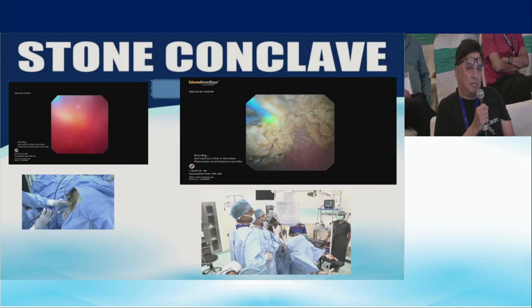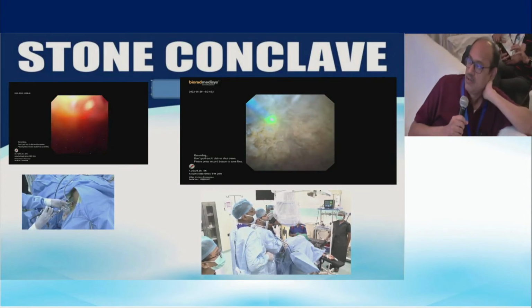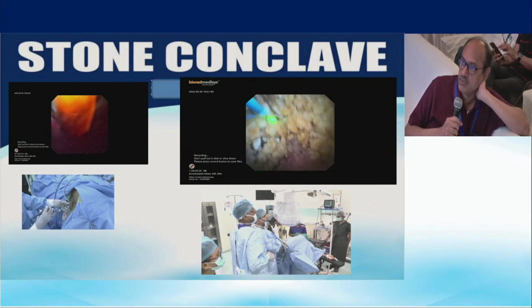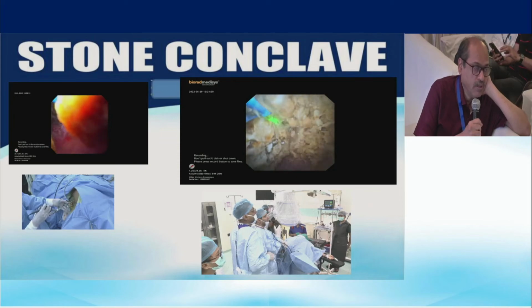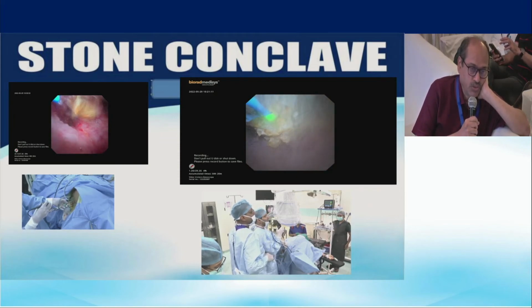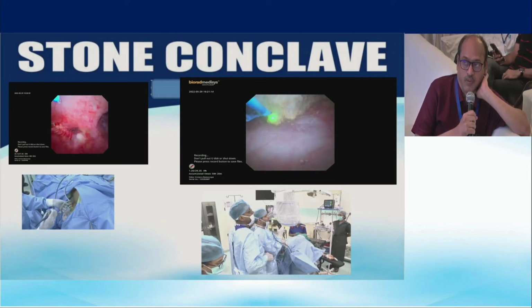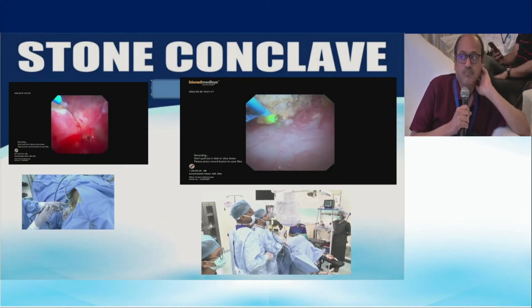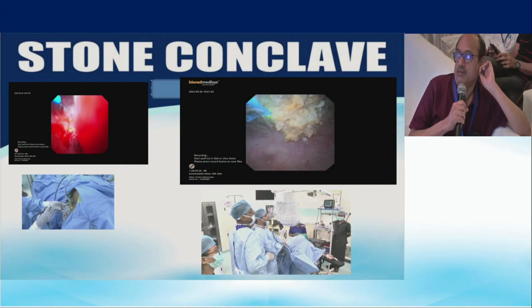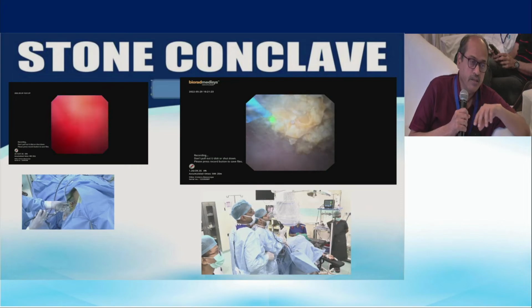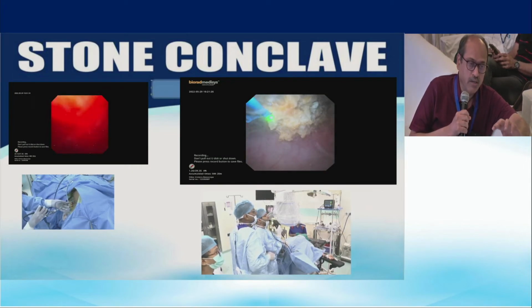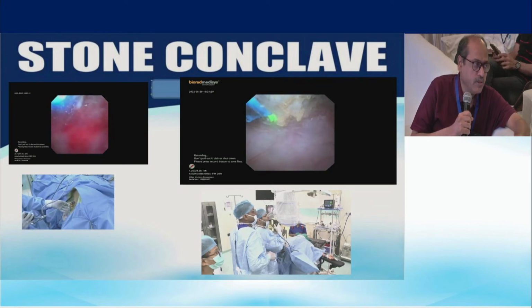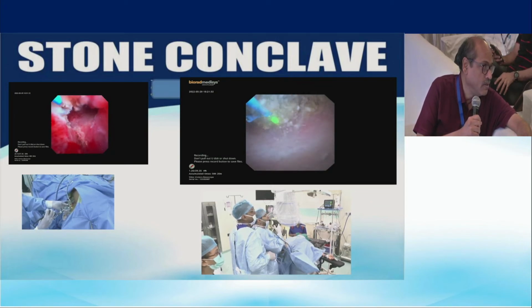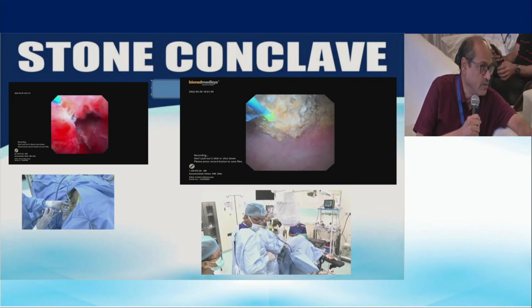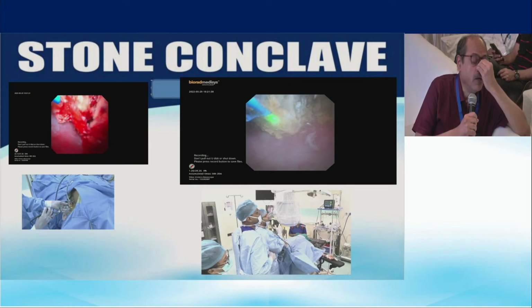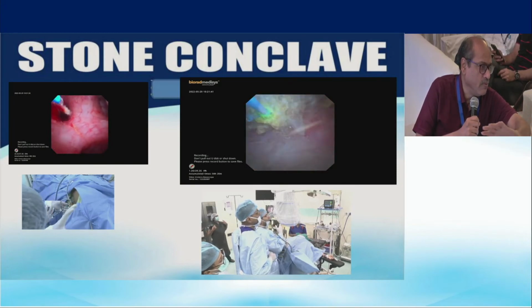If you increase the power, increase the joules, then the size of the fragments formed is going to become slightly bigger and bigger. Yes, correct. If you decrease the joules, then the size of the fragments formed will be smaller and smaller. Therefore, we start with 0.1 and 100. If the stone is slightly bigger or harder, then we go to 0.2 and 100. Most of the time it forms a fine dust with 0.2 and 100. Initially start with 0.1 if it is a dihydrate stone. 0.1 and 100 is more than enough. It will eventually powder everything.